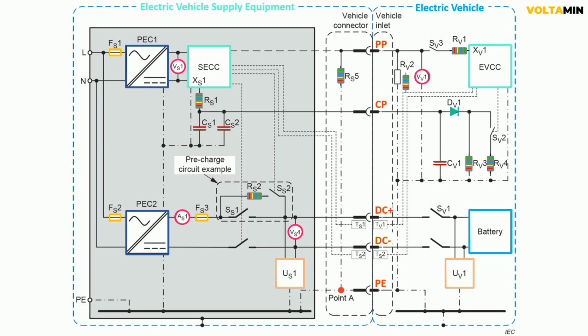AS1, ammeter in EVSE, monitors current flow in the EVSE to ensure it remains within safe operating limits. VS1, voltmeter in EVSE, measures voltage at critical points in the EVSE circuit. There is safety and monitoring, which consists of US1, insulation monitoring device IMD in EVSE, which continuously monitors the insulation resistance of the EVSE to detect potential faults and ensure safety. SS1, switch or relay in EVSE, controls connections during pre-charge and other operational phases.